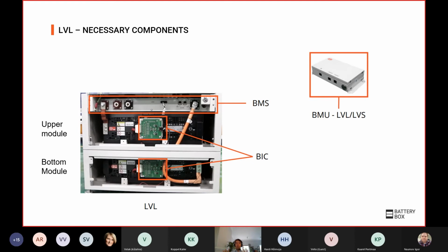The system is composed of two items: the LVL unit itself and the BMU. You need one BMU per system, only one, even if you have 64 of them in parallel, because this is the communication interface with the inverter. Inside the LVL, everything is already assembled and included in the box. You have the BICs that come with each of the modules, which collect the battery voltage and battery temperature data, and the battery management system, which is the tray on the top of the unit, which has all the control logic and the protections of the batteries.